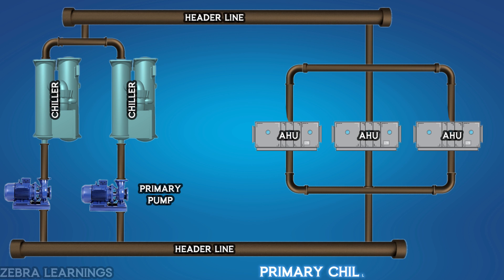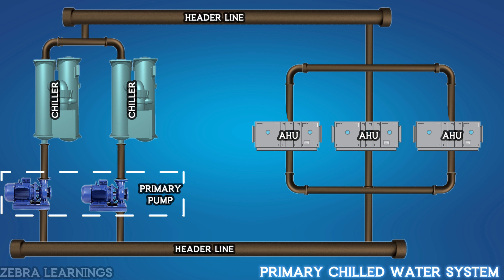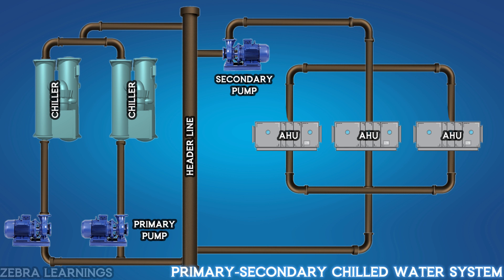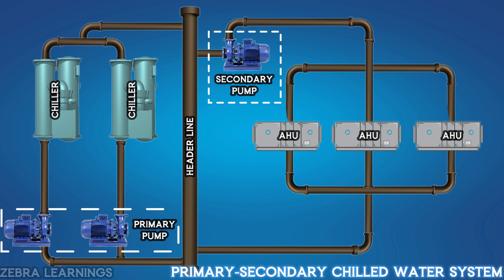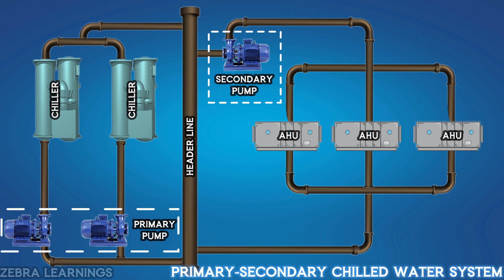In the primary chilled water system, we only use a primary pump to circulate chilled water between the chiller and the AHU. In the primary secondary chilled water system, we use both a primary pump and a secondary pump to circulate chilled water between the chiller and the AHU.